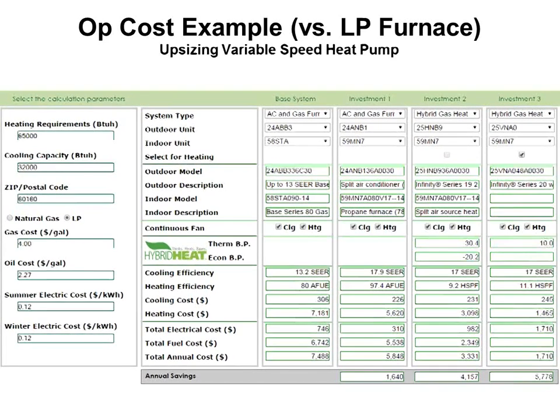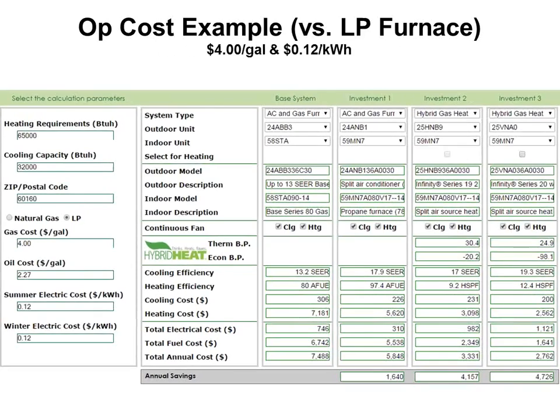So I didn't upsize it here. It's $4,700. I did upsize it there. It's $5,700. Just by going up one size at $4 a gallon for propane, I save an extra $1,000 for this person's house. And look what economically it's telling me. Don't turn the heat pump off until it's minus 98 degrees. Now, I'm not going to wait that long. I have to shut it off earlier, but I can get a lot of capacity out of it until that point.